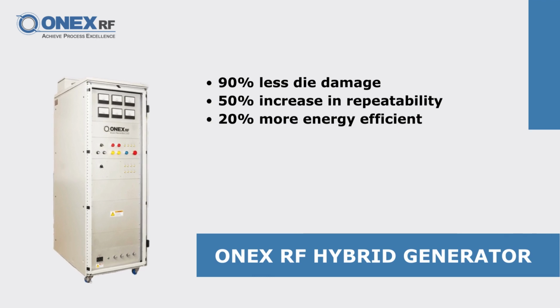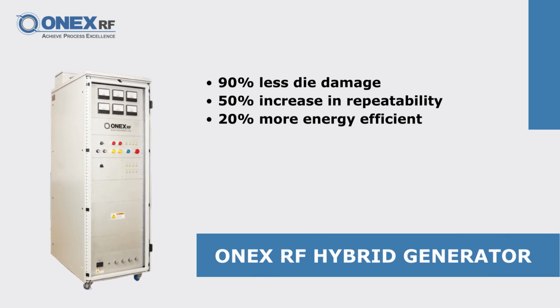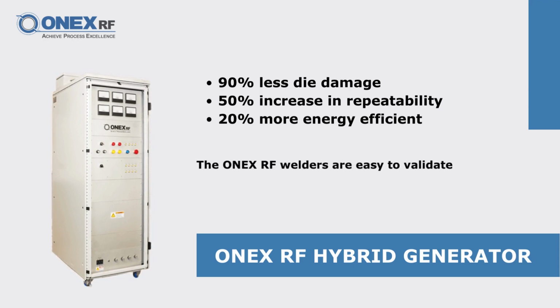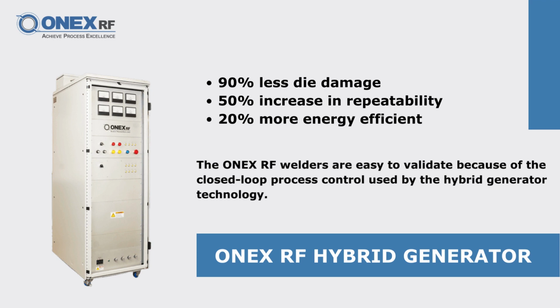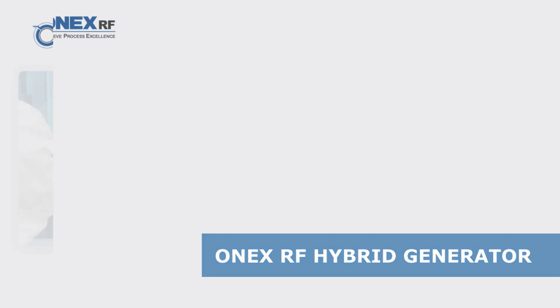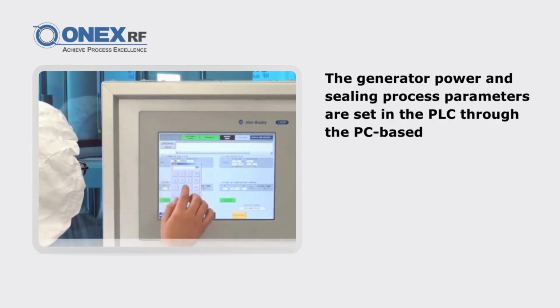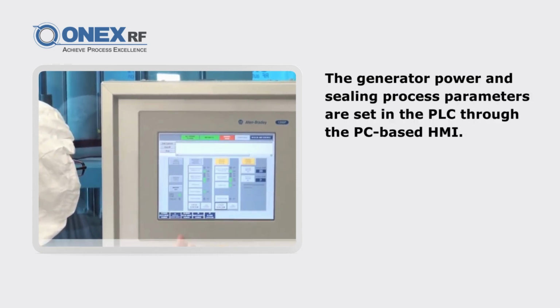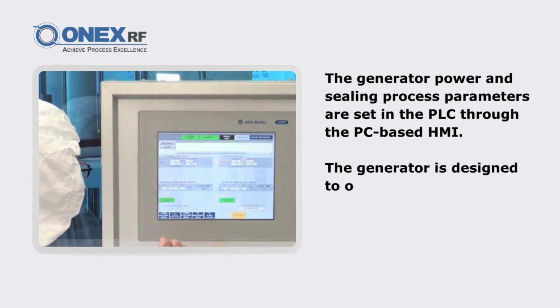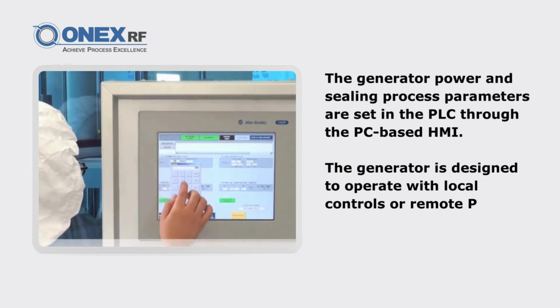They are paired with an impedance match network, designed to sense and automatically reduce the reflected energy. The ONEX RF welders are easy to validate because of the closed-loop process control used by the hybrid generator technology. The generator power and sealing process parameters are set in the PLC through the PC-based HMI. The generator is designed to operate with local controls or remote PLC.